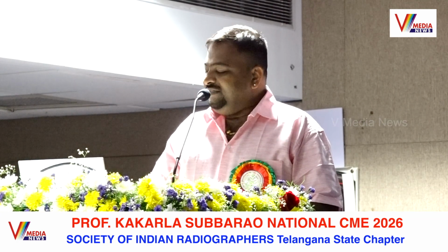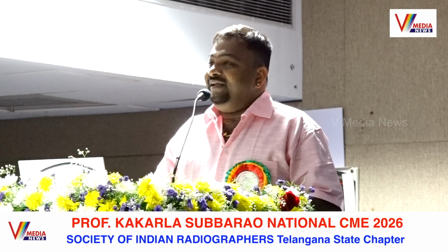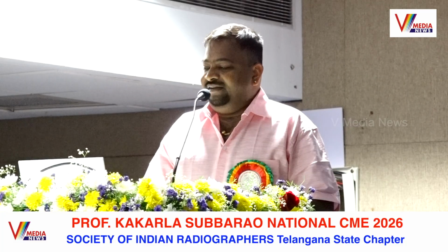To talk on dual energy CT. It was introduced by Hounsfield in 1973 and subsequently by Alvarez and Macovski in 1976. Basically, it acquires images using two energies: one at a higher kV, specifically 140, and one at a lower kV, preferably 80. So dual energy CT allows the analysis of energy dependent changes in the attenuation of different structural materials.